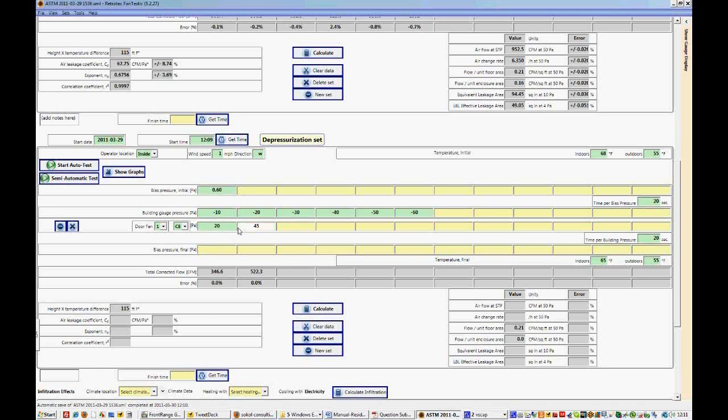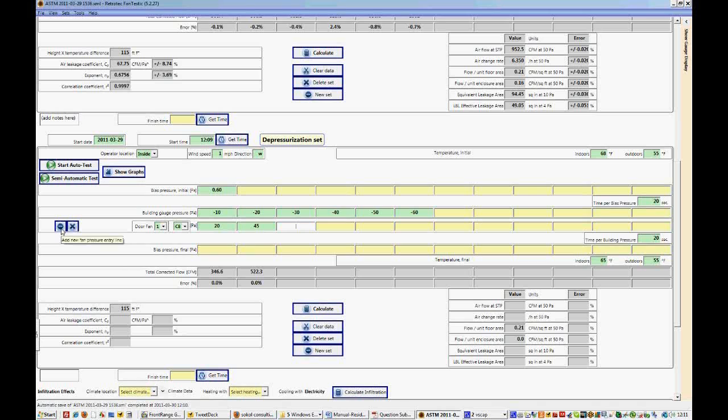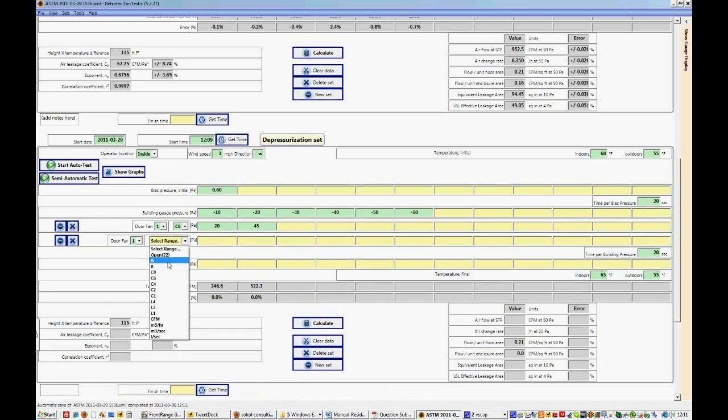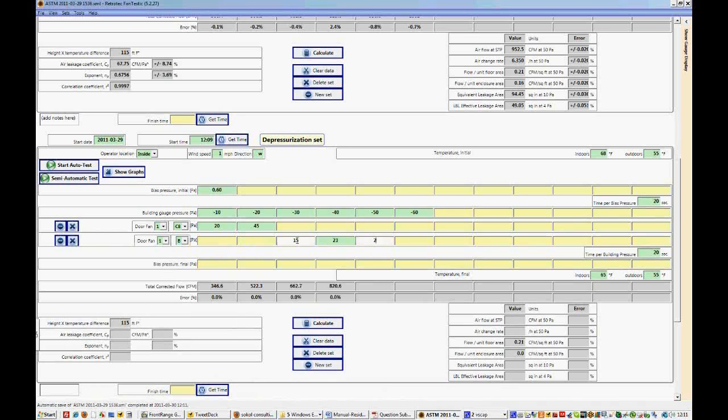But let's say that we decided that halfway through this, after 20 pascals, we wanted to switch up to the B range so that we can achieve 60 pascals easily. So we can't just enter data here and then change this range because that will change it for the entire line and then it will not be accurate. The corrections for flow will not be accurate. So what we do is say New, add new fan pressure entry line.